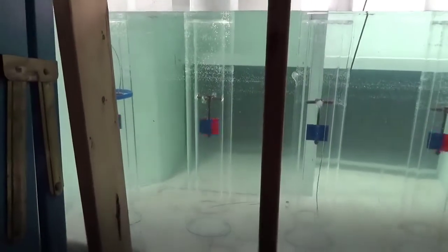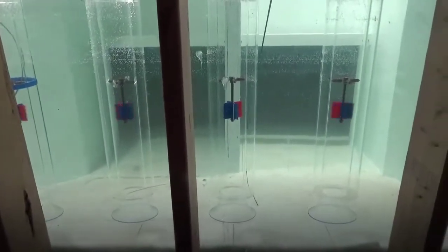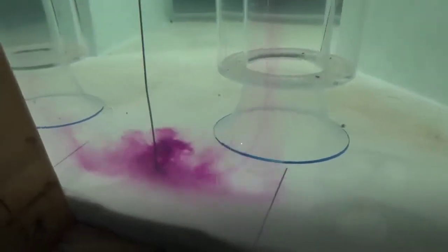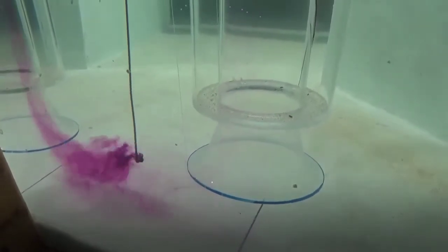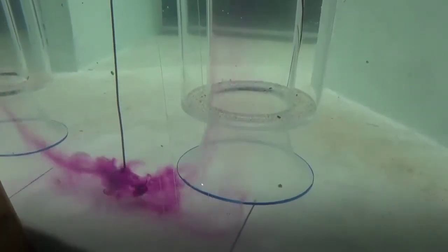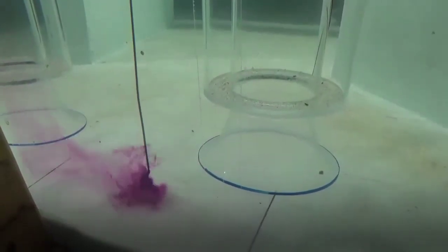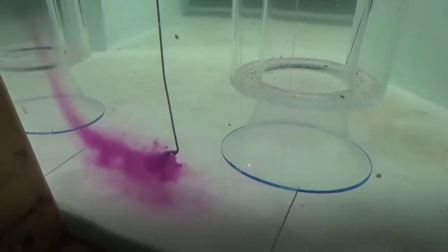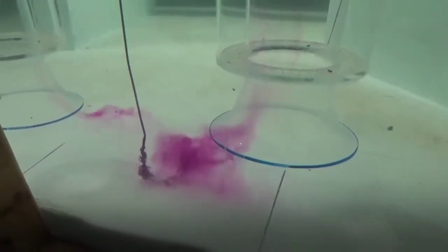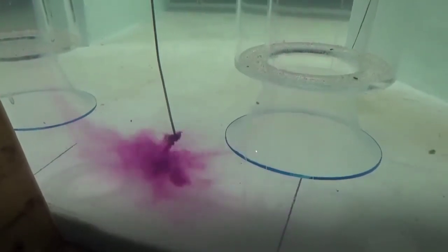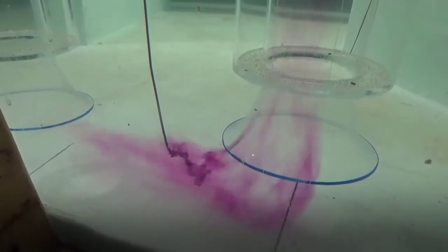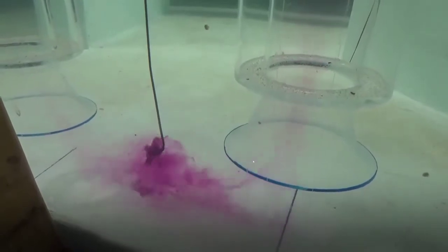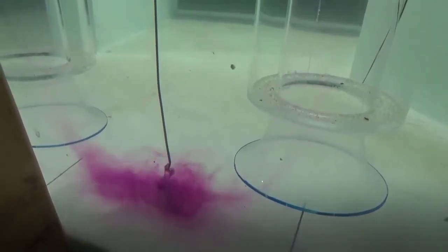We're going to go ahead and go to a, we've got mid-flow vortex activity also. Let's see if we can get into that. That's very difficult to get into these mid-flow vortices. We're going to kind of just watch it for a moment. You'll see there'll be 2 vortexes going into each pump, and they form right in the center. The wall breaks it up. If you watch closely looking for that circulation, you'll see it. We're going to try to get a good shot of it. It was there going good on the right.